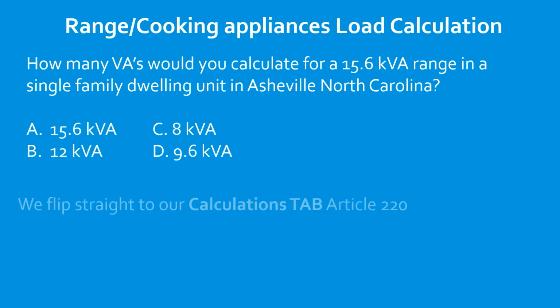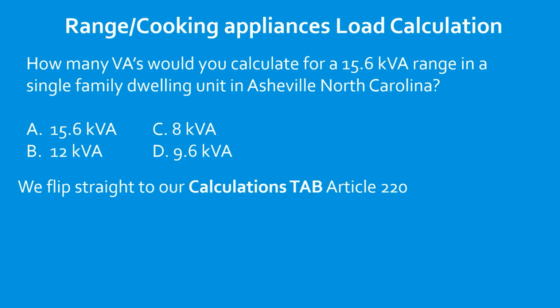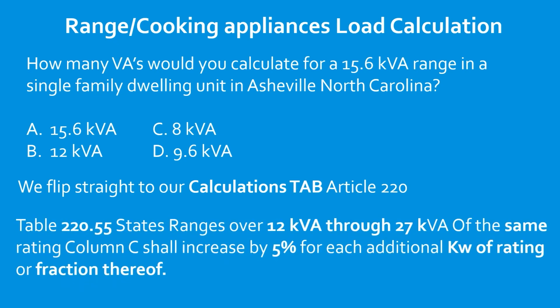How many VAs would you calculate for a 15.6 kVA range in a single-family dwelling in Asheville, North Carolina? So the first thing we're going to do is we're going to flip to our Calculations tab, Article 220, and we're going to decide what column we're working in, or are we using one of the notes. So we check columns A, B, and C. We know that ours is greater than 12, so we're going to be using either note 1 or note 2. In this case, we're going to be using note 1 because we just have one range and it's of equal value.